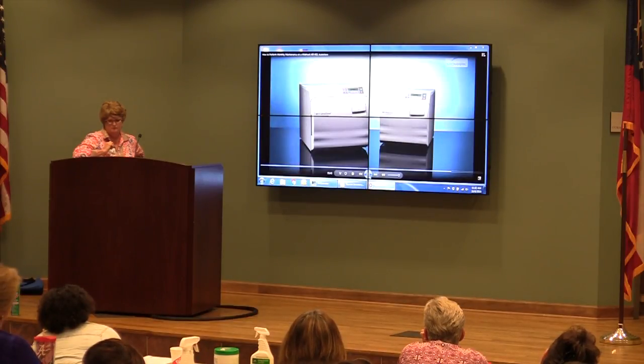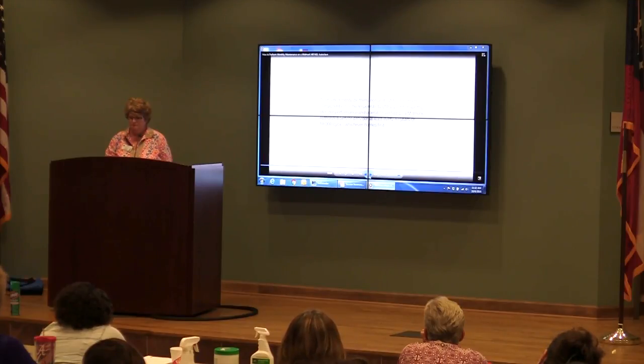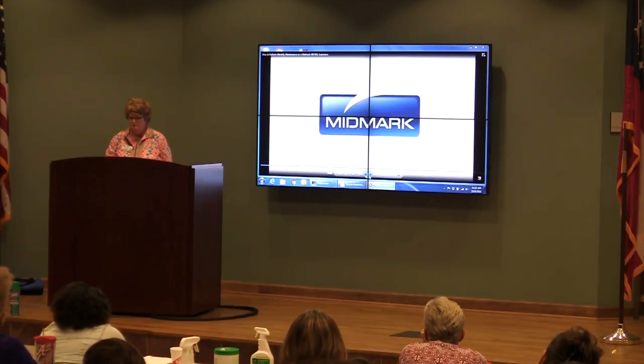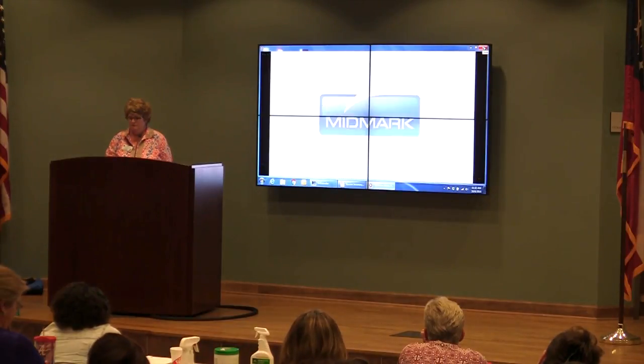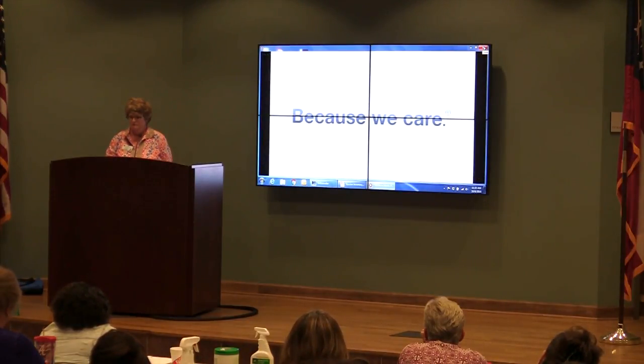M9 and M11s are designed and tested to provide exceptional reliability throughout their service life. To ensure integrity, performance, and safety of all major components, it is the responsibility of the user to have the sterilizer performance and operation verified by a Midmark authorized service provider at least every 10 years or 10,000 cycles, whichever comes first. For more detailed information about maintaining your autoclave, please refer to the M9 M11 Installation and Operation Manual. For further support, contact Midmark Support Services at 1-800-MIDMARK.